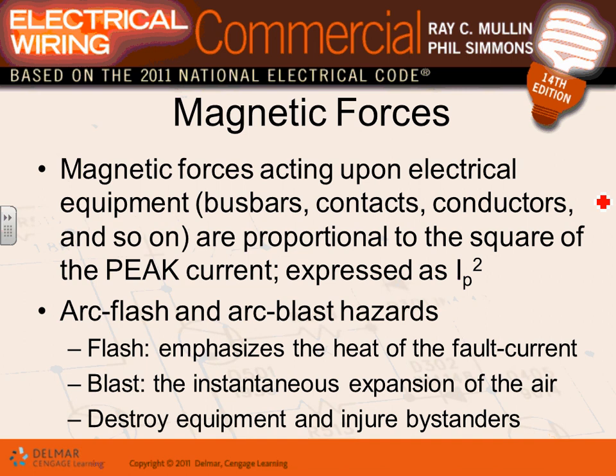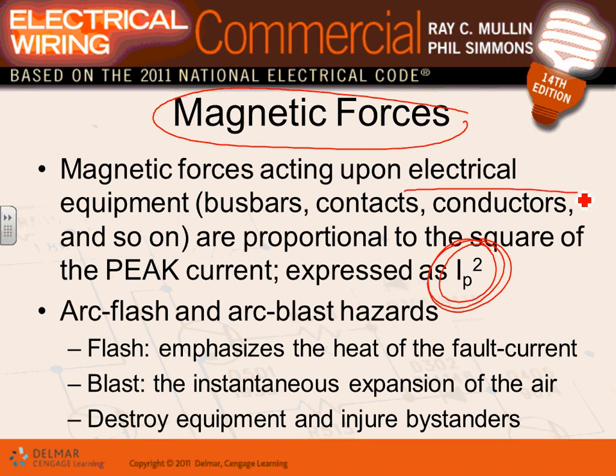Okay, so now that we got the heat and how to calculate the heat, now there's the magnetic field. The magnetic force, yep, it is a square. If you take the peak of this signal, this value here, that's I peak, and you square it, not RMS. Here's the RMS, root mean square, a statistical value. If you take the peak and you square it, that will give you an indication of how much magnetic force is going to be shaking your equipment.